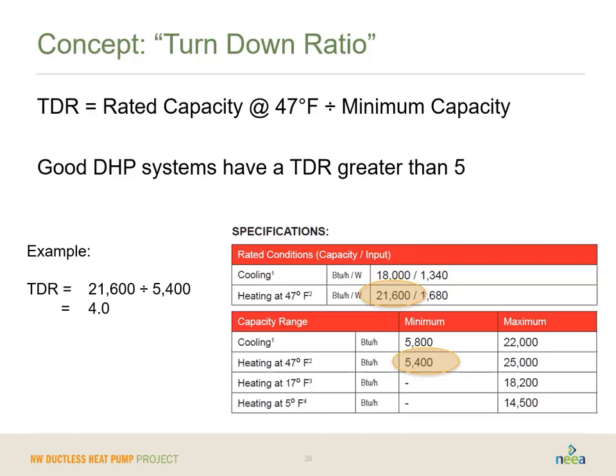Most cold climate ductless heat pumps have a turn down ratio between 3 and 5, but where they really excel is being able to deliver that 85% of the capacity at really low temperatures. So their best job is at really satisfying you when you're really cold. Whereas your standard ductless heat pump with the higher turn down ratio, its best job is being able to satisfy the building when it just needs a little bit of heat. So just two different ways to think about what's really important and really imagining how this addresses the needs of your consumers.